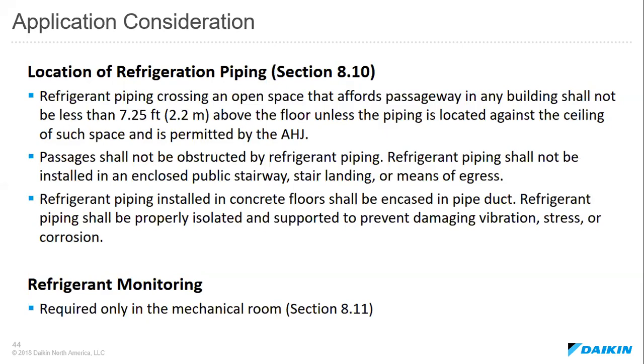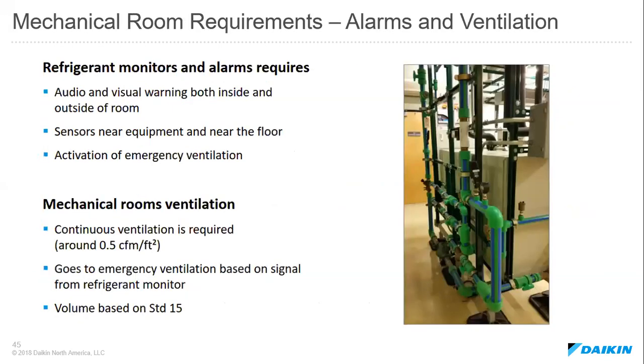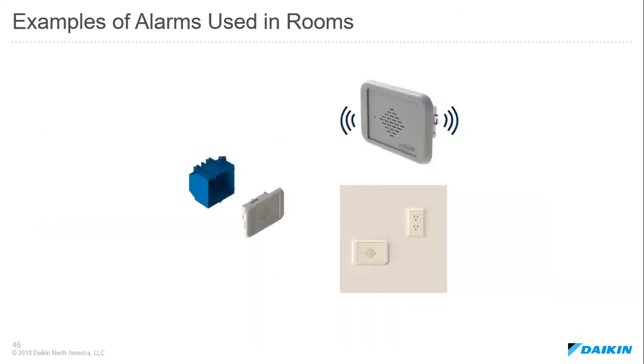And then finally, refrigerant monitoring. Refrigerant monitoring is required for mechanical rooms, and the refrigerant monitor in the mechanical room needs to have audio and visual warning signals. It also has to have sensors near the equipment or the floor, and needs to activate emergency ventilation. Continuous ventilation is also required in mechanical rooms, and this has to be around 1/2 of a CFM per square foot of the space. Then we'll go into emergency ventilation based on a signal from the refrigerant monitor, and that volume is going to be based on ASHRAE Standard 15. Here's an example of the alarms used in the rooms.